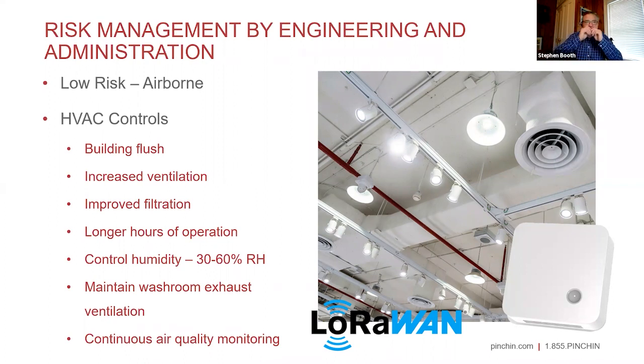So this idea that these very small droplets can occur when we breathe and then float, that's driven a little bit by humidity. So if we maintain humidity well between that 30 to 60% range, that's going to help minimize those risks. And then I think, both for the cleaning and for the ventilation, providing some monitoring that confirms that, yeah, we really are providing additional ventilation, and here's the proof. And on cleaning through ATP or total bacteria samples to say, hey, not only do we say we're cleaning, but look, here's empirical evidence that the cleaning is working and keeping surfaces clean.